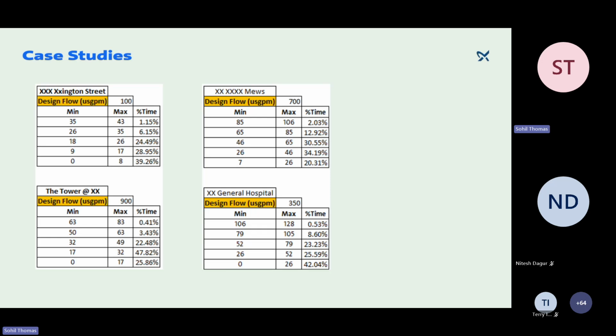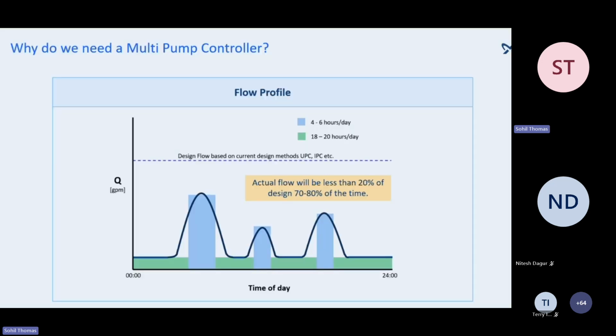So what happens, as you saw in my last slide, is it would actually run towards the left-hand side of the curve, go below that minimum continuous stable flow, and that creates thermal flow issues. The reliability, the efficiency, the power demands, everything is going to affect the pumping systems if they are not right-sized. So that's why it is very important to size the pumps at the right point.